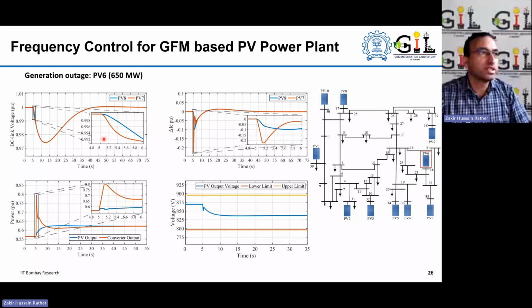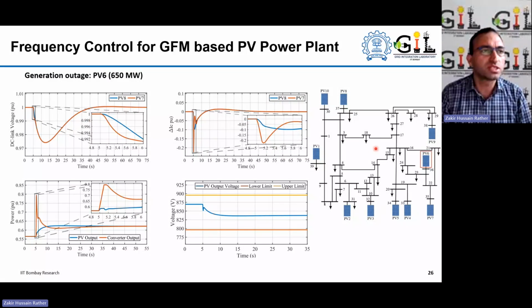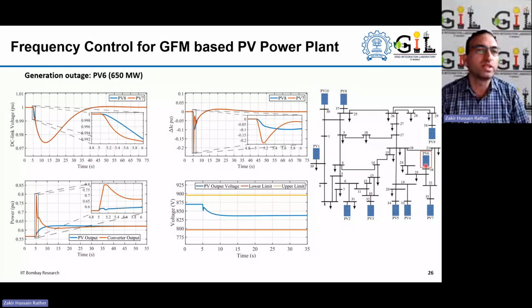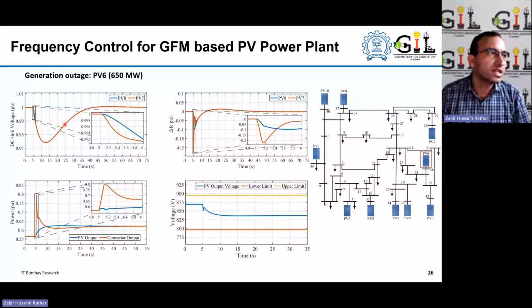Now, the response you can see here of these other grid forming power plants, here we have shown only PV7 and PV8 as representative results of this study. You can see here, PV power plant 7 is closer to the disturbance, while power plant 8 is a little bit farther from the disturbance. So you can see here the response of these two. The DC link voltage of the plant which is closer to the disturbance, that is PV7, is actually getting more disturbed.